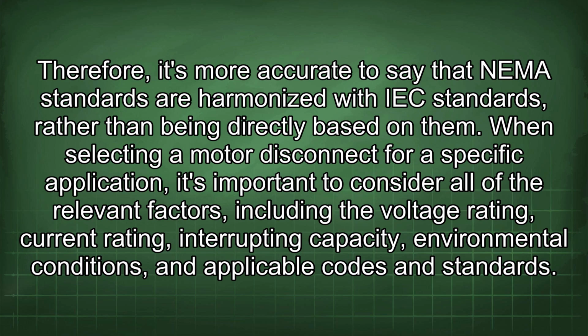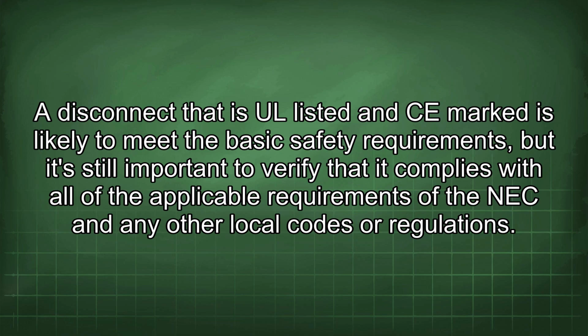When selecting a motor disconnect for a specific application, it's important to consider all of the relevant factors, including the voltage rating, current rating, interrupting capacity, environmental conditions, and applicable codes and standards. A disconnect that is UL listed and CE marked is likely to meet the basic safety requirements, but it's still important to verify that it complies with all of the applicable requirements of the NEC and any other local codes or regulations.